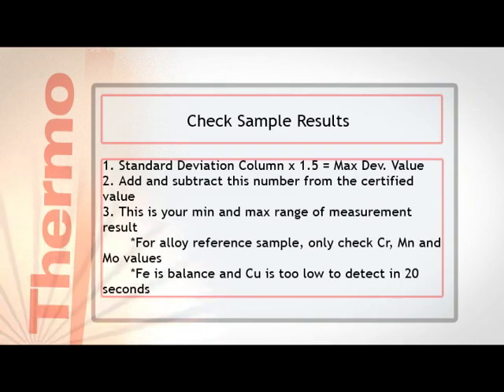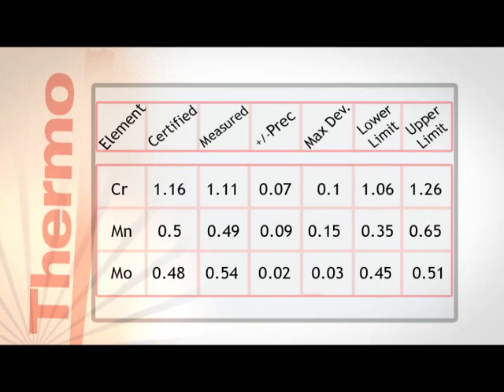We also do not include the copper concentration in our normal calibration evaluation, as it is too low for reliable detection in 20 seconds. We've entered the reference sample results into this table. This is from the last measurement. This will allow us to provide an example of the measurement results. We see, for example, the element chromium is certified at 1.16, whereas we measured it at 1.11. However, we see the precision for 2 sigma was plus or minus 0.07.